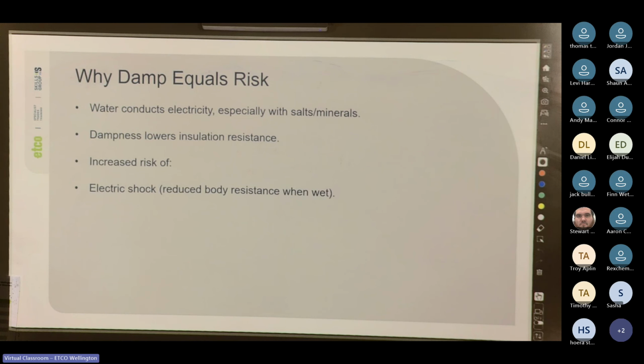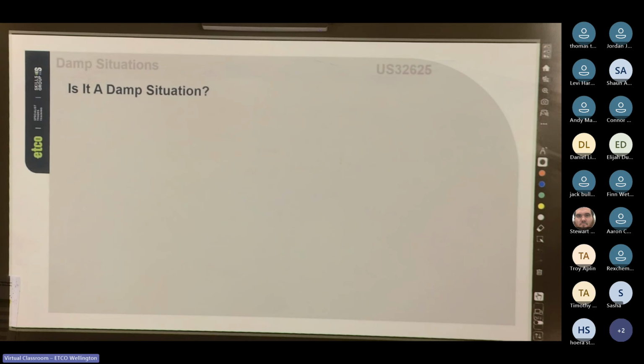Cool. So you get an increased risk of electric shock because of our reduced body resistance when it's wet. Also fire, equipment damaged by the moisture, potentially arcing. And then, is this a damp situation? Yeah, definitely. It's a bathroom. There's the shower, the sink, possibly a bathtub. There's a lot of areas we need to be aware of. So it's definitely a damp situation. Definitely tick.